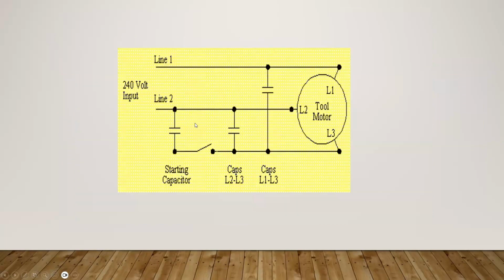And what they do is they simulate, this is called a static phase converter. And what it does is, again, it simulates putting a capacitor in to start it onto one phase. And then it has this run capacitor that sits there and feeds it. And then has another capacitor that comes off the other line to feed that third leg. And all of that is to create a phase shift so that the motor can actually get up to speed.